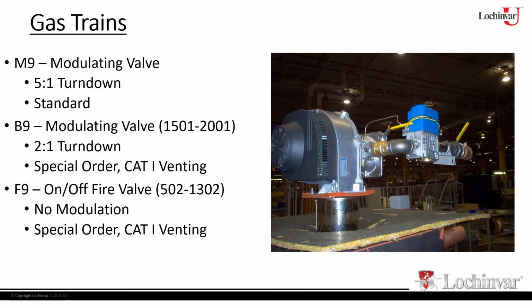Now, F9 applies to the smaller models, again, 500 to 1.3. Same thing, retrofit applications. I've got an original power fin that was B-vented. I want to go back with a B-vent system. So again, category 1 venting. Here, we're going to go back to an F9 model, single stage on off. It's going to be just like it was before. But with this unit, we're going to change gas trains, and we'll look at that in a second. We'll see the different gas train here. So it's going to be a single stage on off, and it's no longer negative regulation. This will be a positive pressure system. So it's a little bit different.